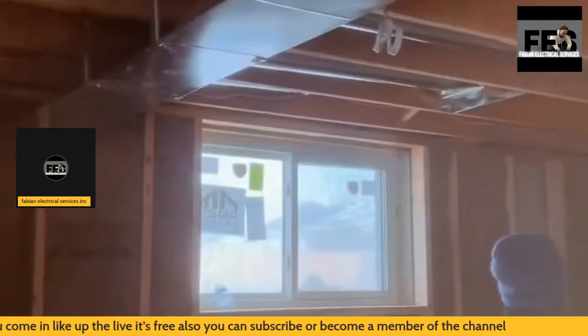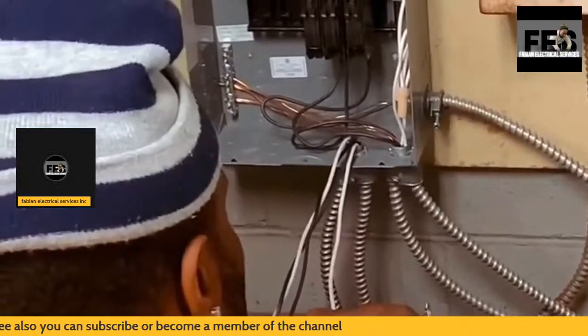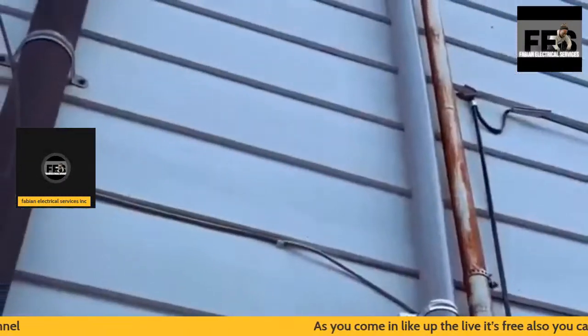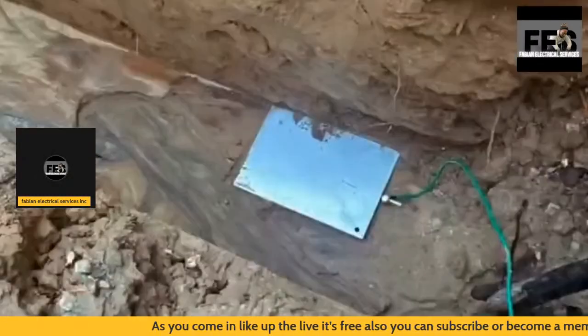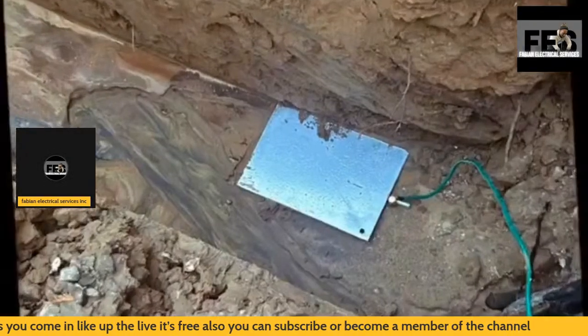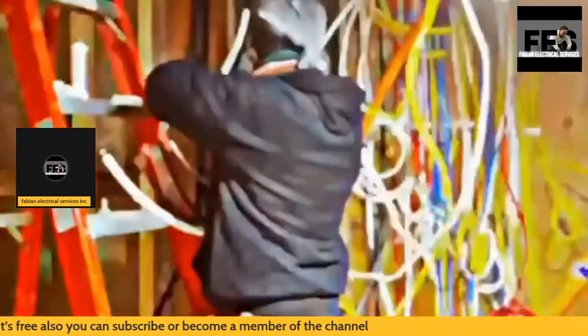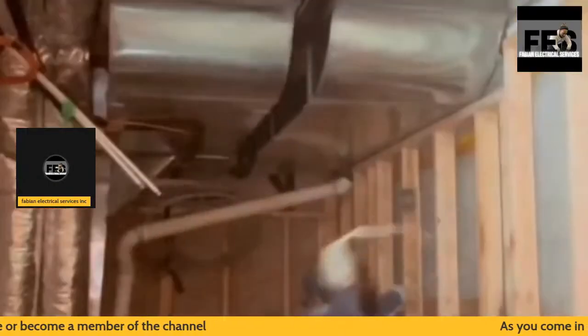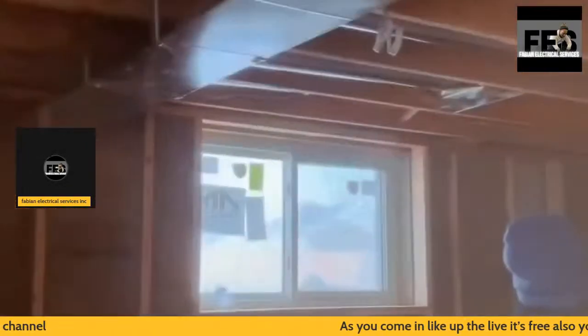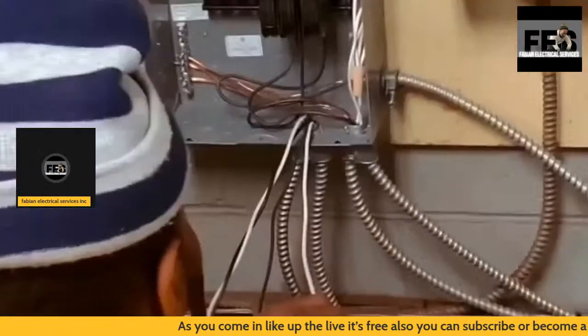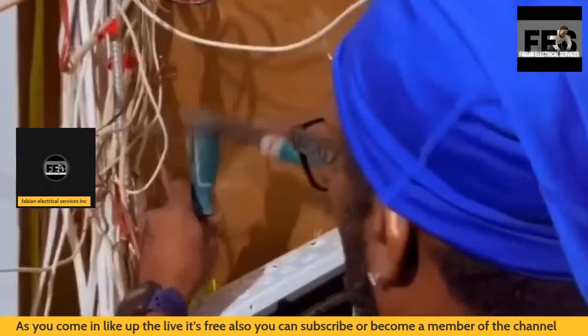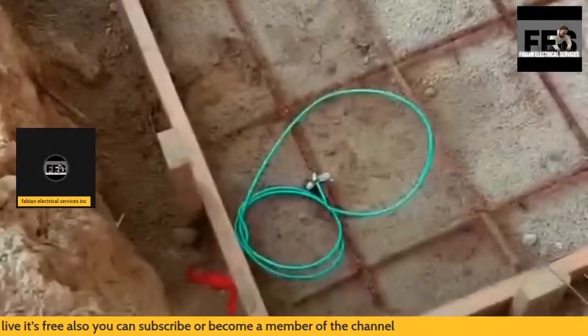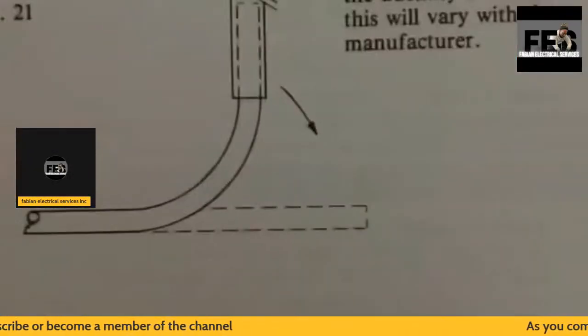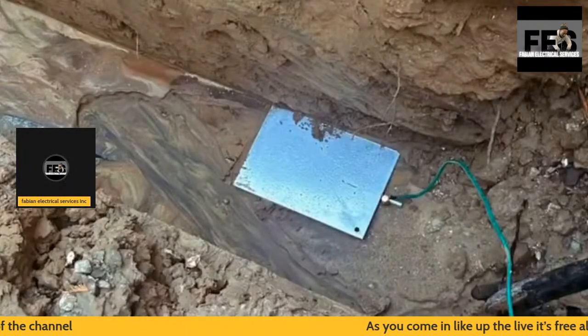Also you'll see me using the ground bushings for the ground wire. This is a bonding and grounding installation, so I have to ground off my main ground wires. I also have to bond off my wires coming from the actual ground plate in the floor. The ground plate you'll see in the back stream that's playing is the actual ground plate used in the installation of this service. So that's pretty much the scope of that installation.